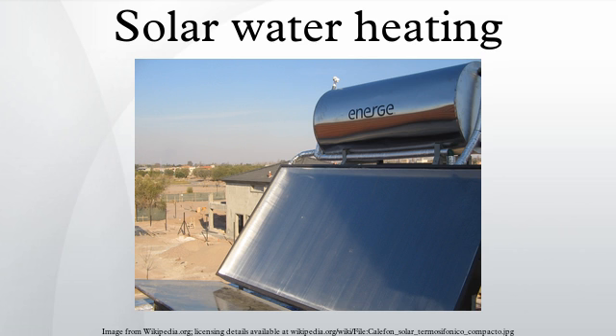SWH systems are designed to deliver hot water for most of the year. However, in winter there sometimes may not be sufficient solar heat gain to deliver sufficient hot water. In this case, a gas or electric booster is used to heat the water.